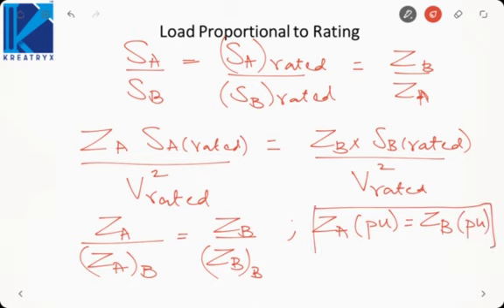But this time both have their individual bases. Earlier I was telling you, when we are applying parallel operation, both must be on the same base or both must be in absolute values. But here, if you want to divide the power based on their kVA rating, or power must be proportional to their kVA rating, then their per unit impedances must be equal, where per unit impedance is defined on its individual base. So remember, for parallel operation, the values that you are substituting must be on the same base or both must be in ohms. But if you want the load sharing to be proportional to kVA rating, then their per unit impedances on their individual bases must be the same. This is the condition for the power division proportional to kVA.